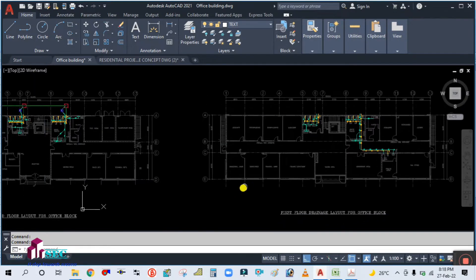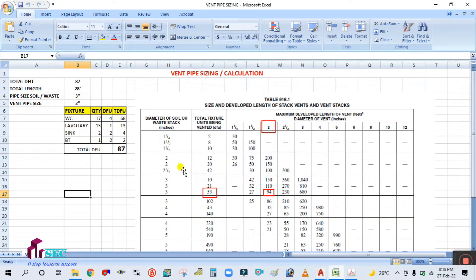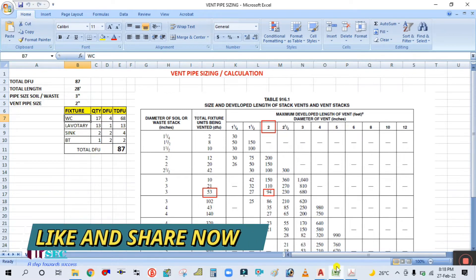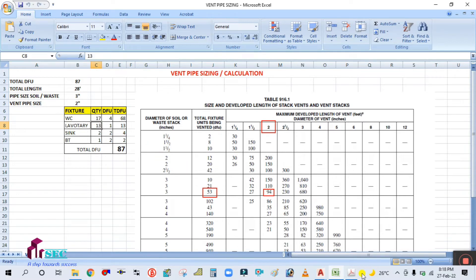Including ground floor and first floor, the total WC fixture is 17, and the drainage fixture unit is 4 for WC, taken from IPC also. So if you multiply: 17 into 4 equals 68.